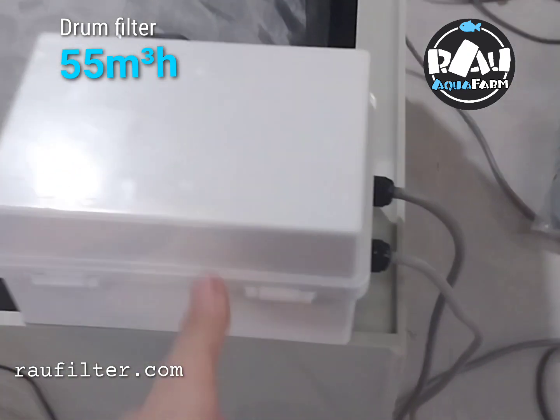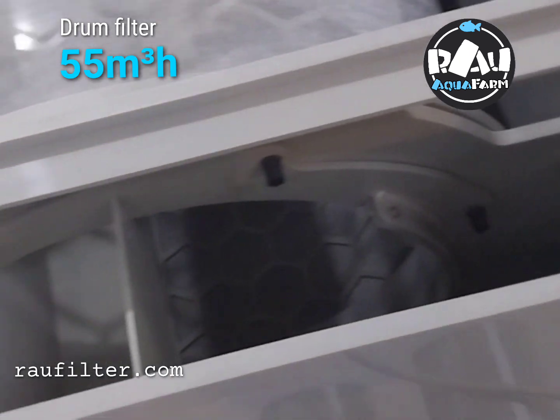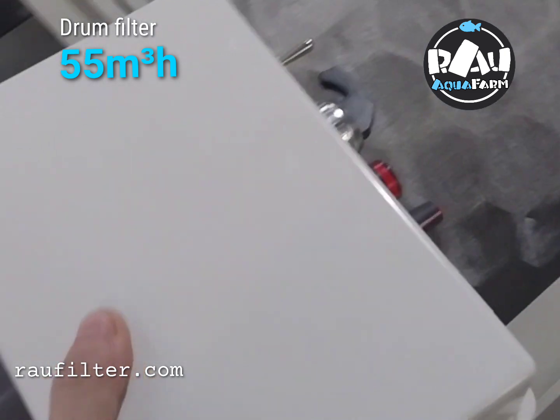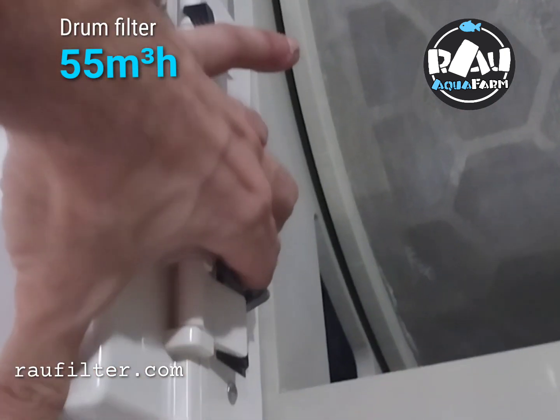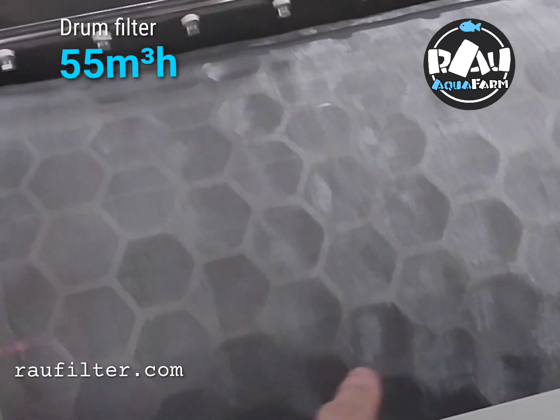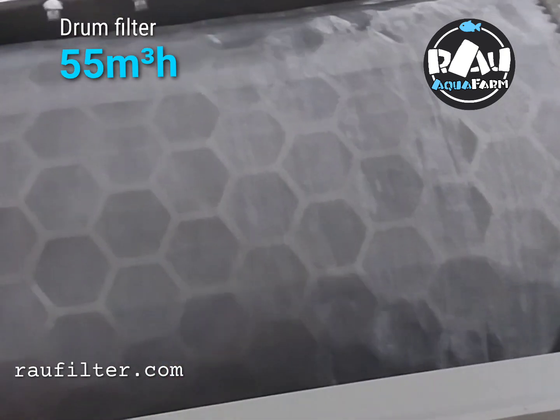Now I check the control box before sending. This control box — inside — and float switch. First, open control box. Here, it has a light. Now open timer. You can see — I put timer 15 seconds, and 30 minutes it stops.